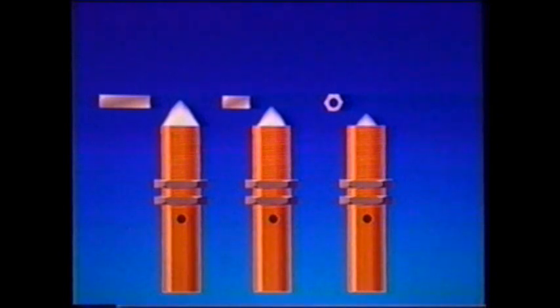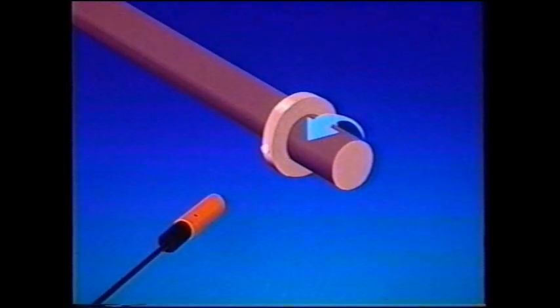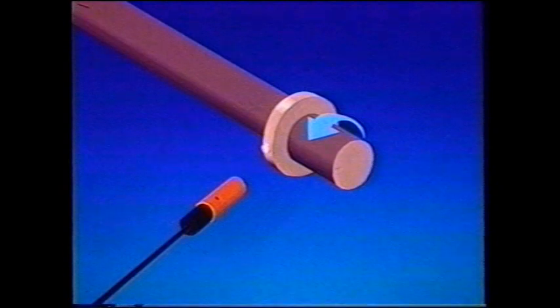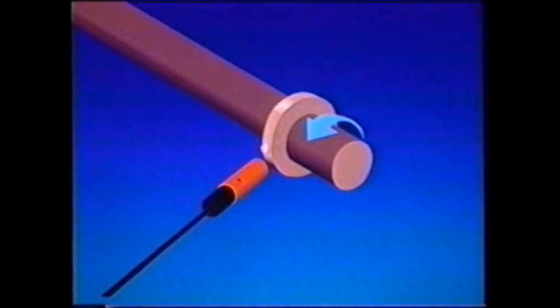Shapes that present smaller cross sections, such as cylinders, spheres, or screw heads, will result in a still shorter sensing range. For example, a bolt in a rotating shaft will not provide the specified sensing range. In an application like this, adjust the switch by moving it closer to the target until the LED just comes on. Then move the switch 50% closer to the target. This will put the switch at the midpoint of its range for reliable operation.